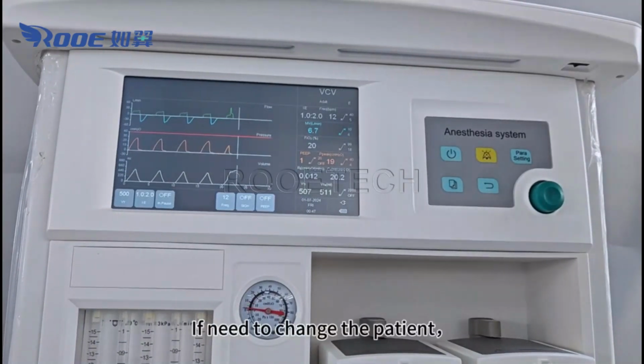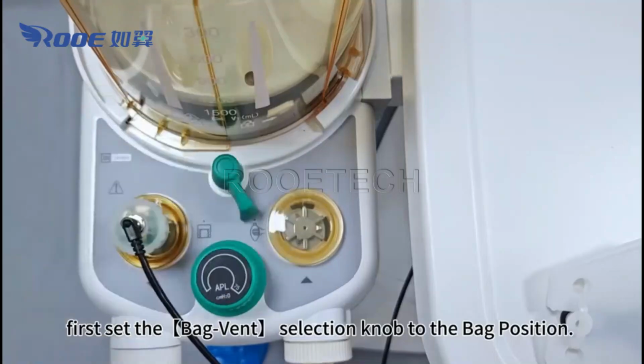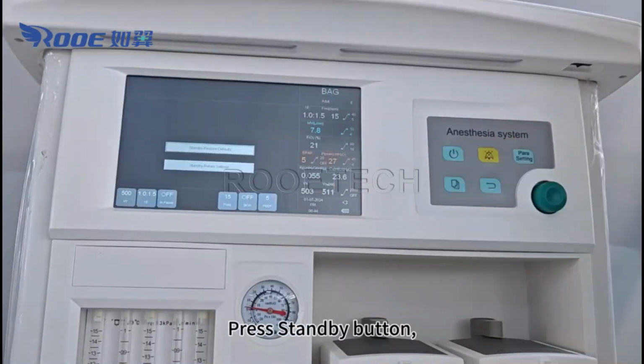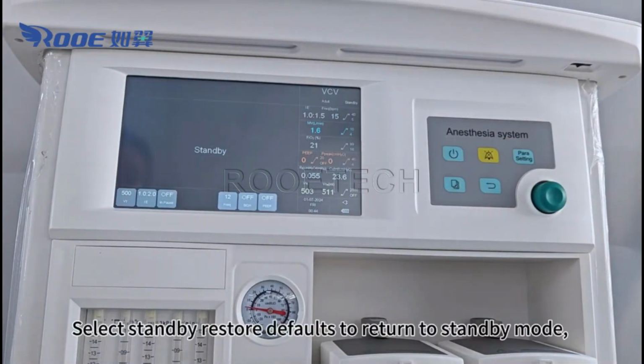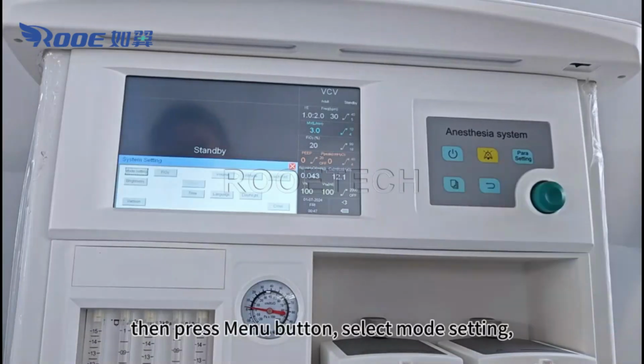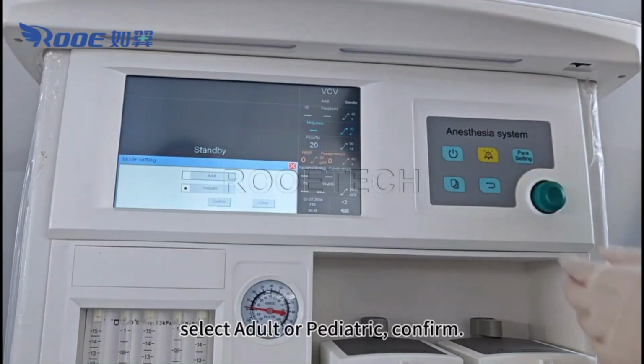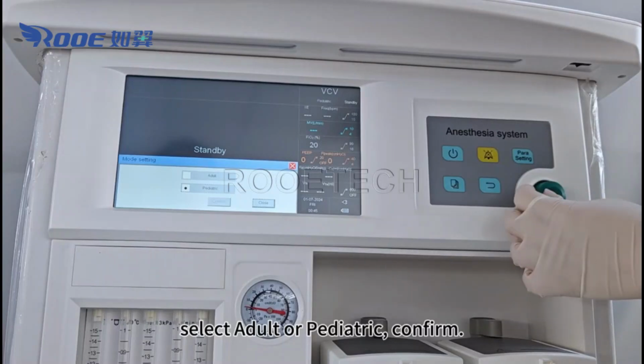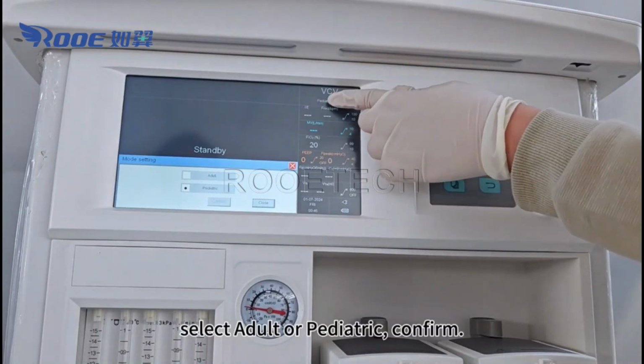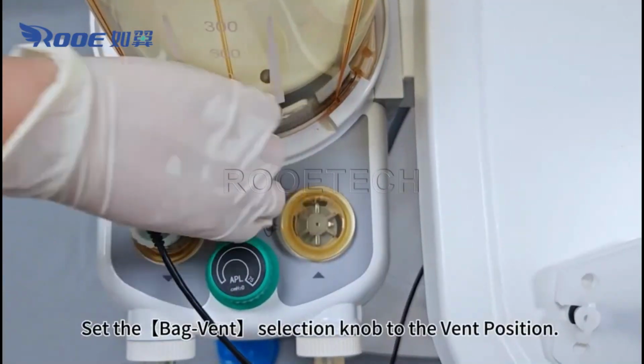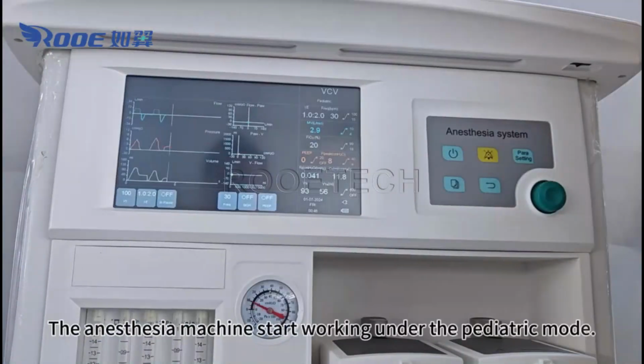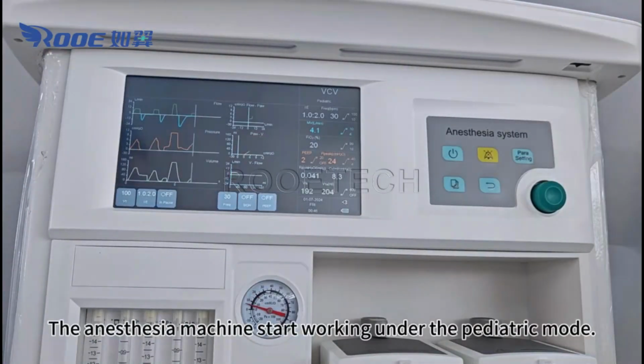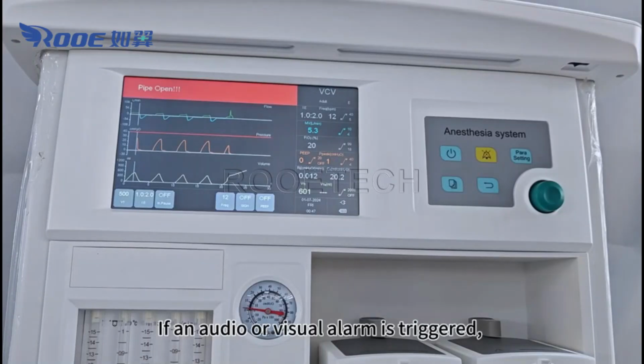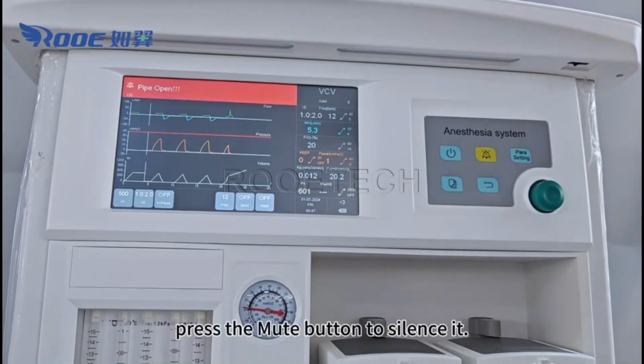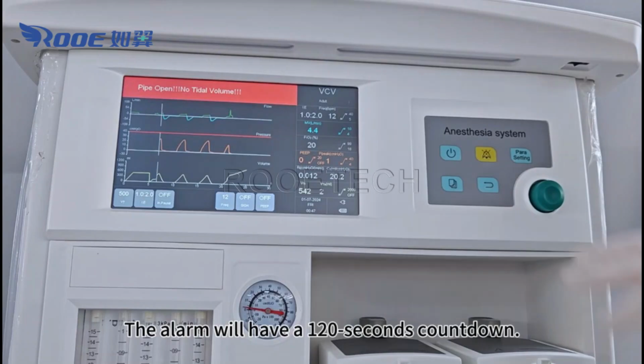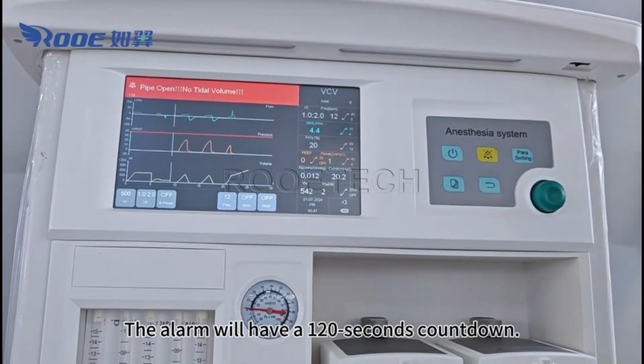If need to change the patient, first set the bag vent selection knob to the bag position. Press standby button, select standby, restore defaults to return to standby mode, then press menu button, select mode setting, select adult or pediatric, confirm, and set the bag vent selection knob to the vent position. The anesthesia machine starts working under the pediatric mode. If an audio or visual alarm is triggered, press the mute button to silence it. The alarm will have a 120 seconds countdown.